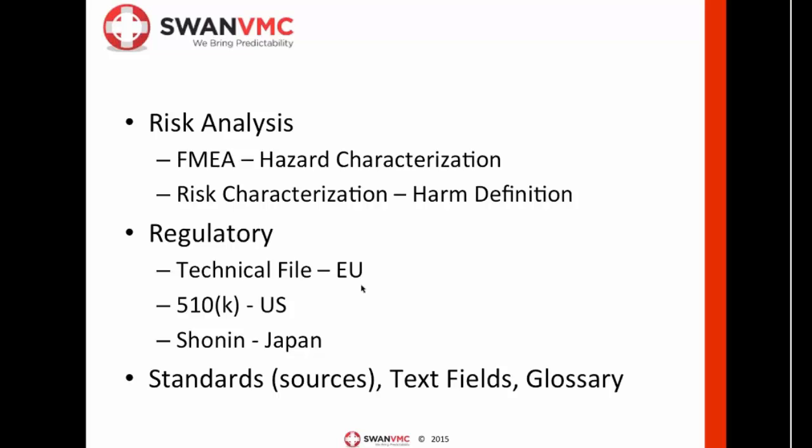Same thing for the 510K. If you pull those major categories in, and the requirements in, not a requirement particularly, that's probably the wrong word, but to delineate what the needs of the 510K are, and then take all the output that we're developing as part of this design control file, we can copy them in directly. So what's going to happen is, as you're building your design control, you're going to be populating your 510K. And of course, the really great thing about that is it pushes regulatory into the development of that file very early in the process.